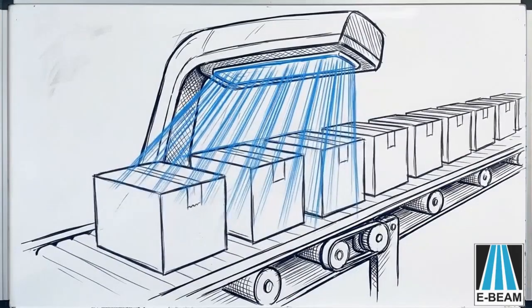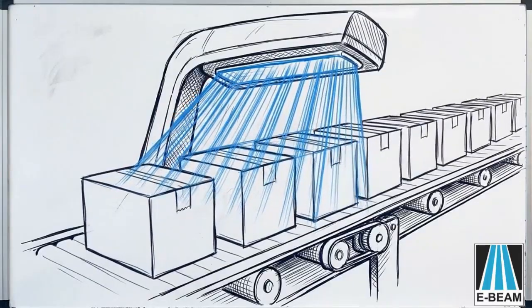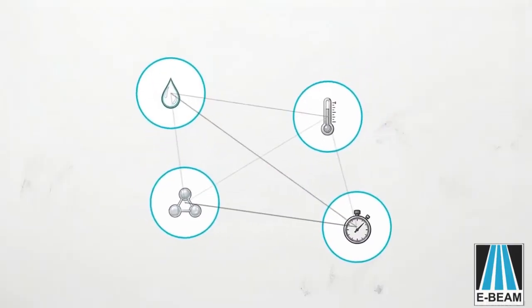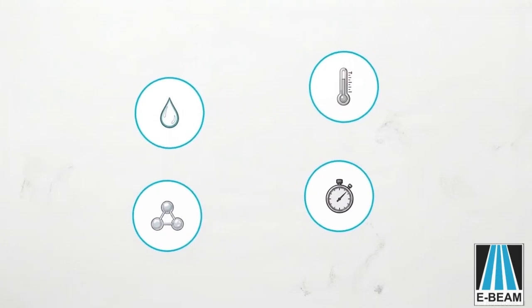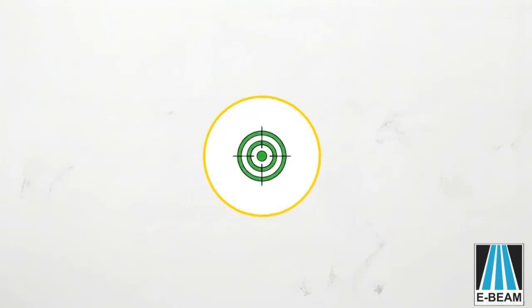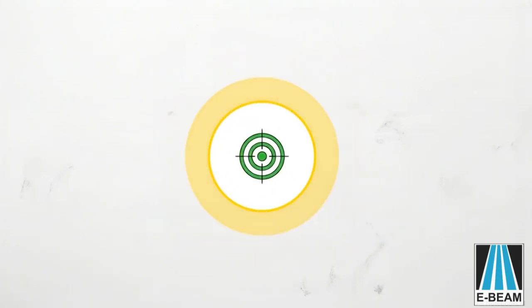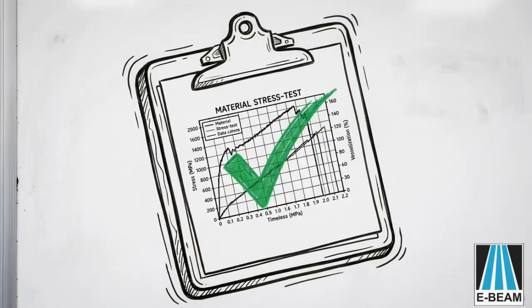Electron beam sterilization takes a completely different approach. Instead of managing a gas process with 4 interacting variables, sterility is achieved through a single, precisely measured radiation dose. Not every product is a good fit for ebeam, but this one checked all the boxes.